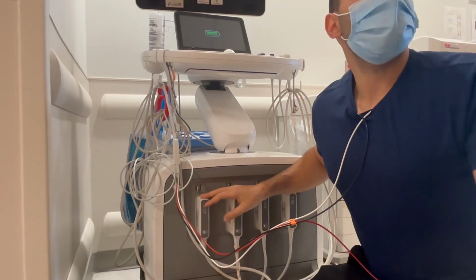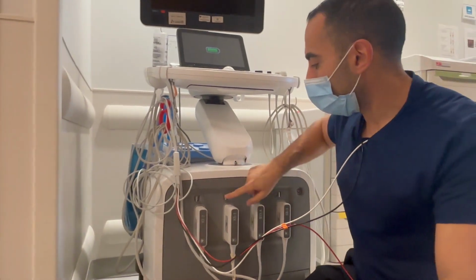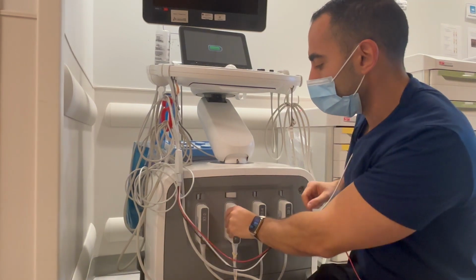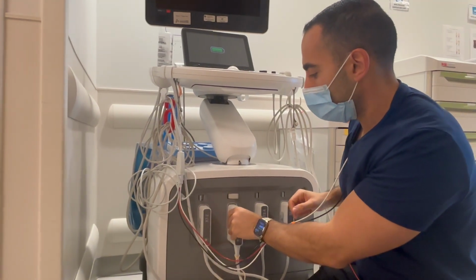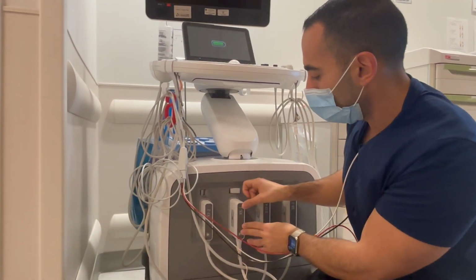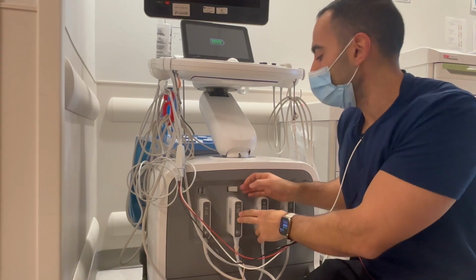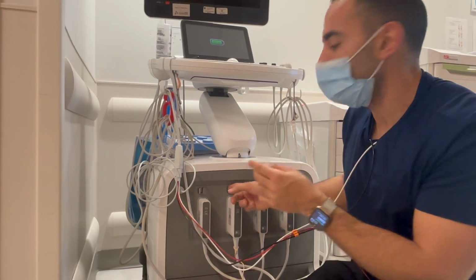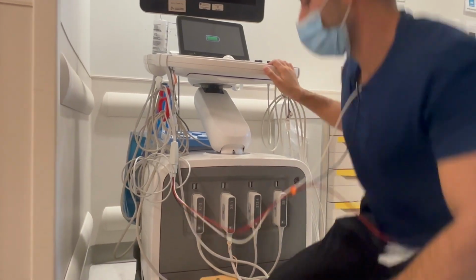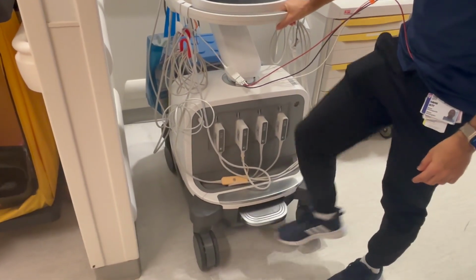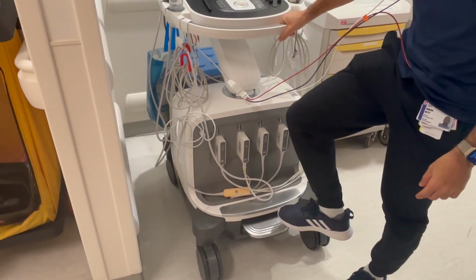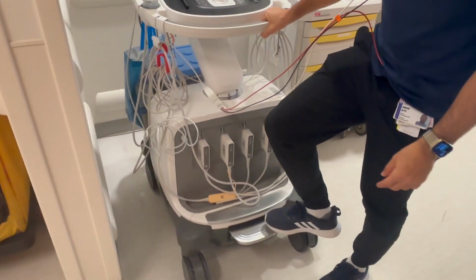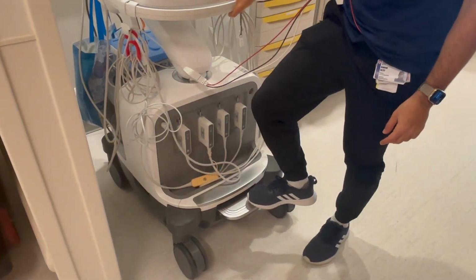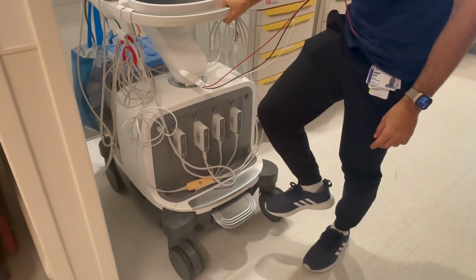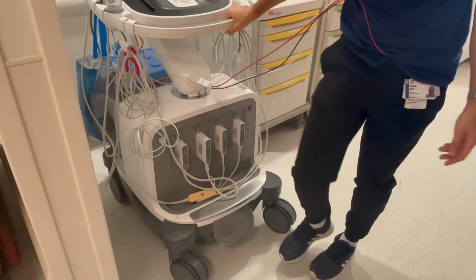Let's say the probe, as I mentioned, is not attached to the machine. It's very easy. You can detach like this and then attach just by gently pushing. There's really not much pressure to be applied, to avoid breaking the probe, and then you reclose it in the safety position. The machine has a pedal that goes in 3 positions. The first position is rolling in only one direction. The second position is to roll in all directions, and the third position is to lock it.